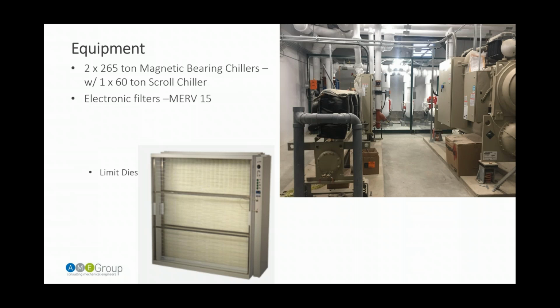Electronic filters, and the reason that we looked at this was because our intakes are about 5 stories up from it, but they're above the generator exhaust. And we wanted to make sure that we didn't have issues with the generator exhaust whenever they are testing it, or should the building go down and researchers think that the building has issues when they start smelling generator exhaust or diesel fumes in the building. So that was the primary driver of that.